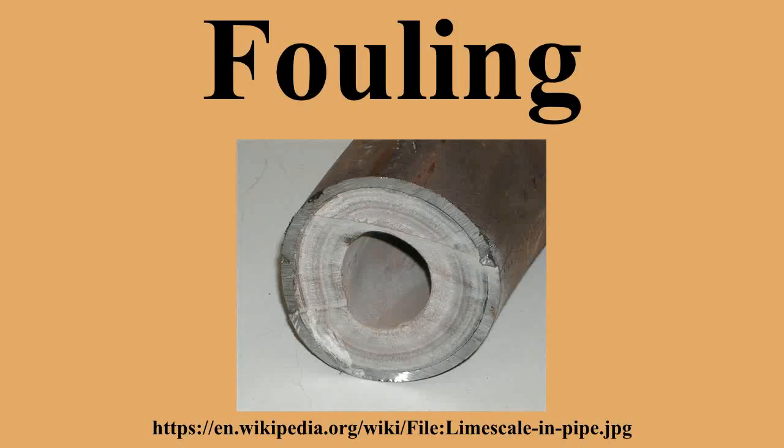Chemical fouling inhibitors can reduce fouling in many systems, mainly by interfering with the crystallization, attachment, or consolidation steps of the fouling process. Examples for water systems are chelating agents, long-chain aliphatic amines or polyamines, organic phosphonic acids, or polyelectrolytes. For fired boilers, aluminum or magnesium additives can raise the melting point of ash and promote creation of deposits which are easier to remove. See also process chemicals.